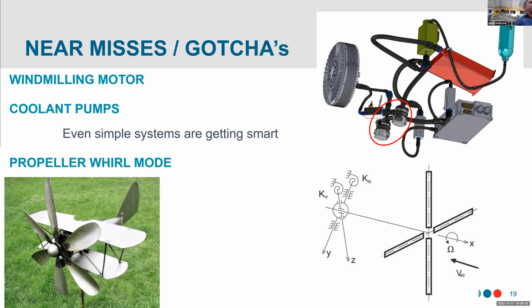I'm a coolant pump - if the coolant's at 0 degrees, why am I working so hard? It automatically derates to 50%. We went back, talked to the manufacturer, and he said, oh yeah, I should put that in the data sheet. We had no idea these pumps were actually smart with this auto-derate function. So we're working our way through that. We're using pressure switches to indicate a system fault, and of course when the pump derated, the pressure dropped low enough that we started getting these lights.